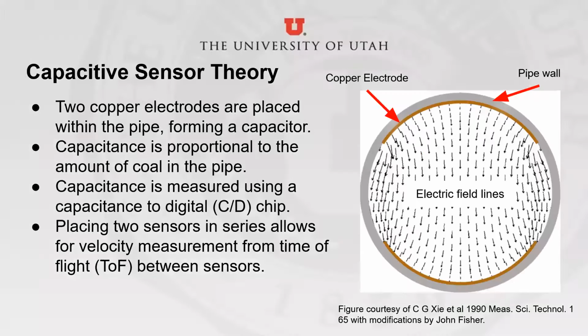How does it work? 2 copper electrodes on either side of the coal flow form a simple capacitor, and the surrounding steel pipeline acts as an electrical shield. Coal has a higher dielectric constant than air, so as more coal enters the sensing field between the electrodes, the capacitance increases. The net dielectric constant between the electrodes, and hence the total capacitance, is a linear function of the proportion of coal in the pipe.